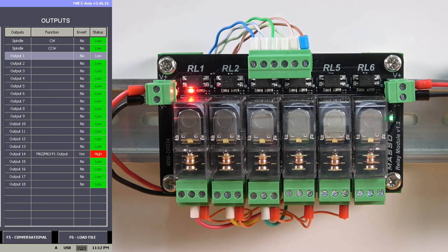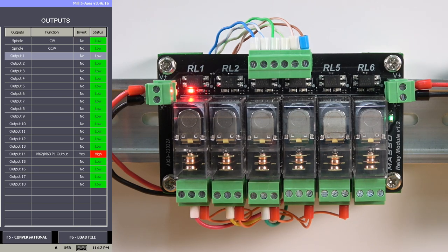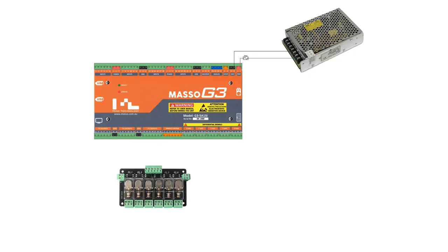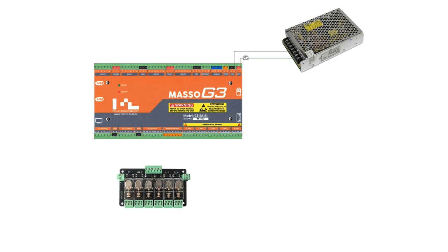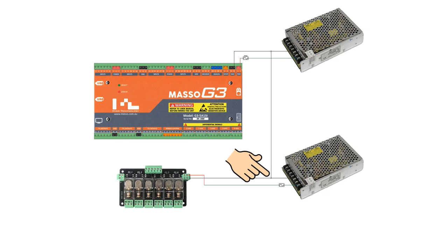To connect your relay module to Masso, start by connecting the 24-volt power supply to the relay module. If you are using a separate power supply, please ensure that you common the negative of the relay module's power supply to the negative rail of the Masso power supply, or the inputs will not work.